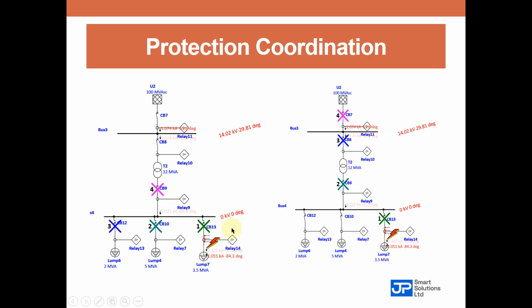But in a situation, what if this relay is no longer functioning properly? What if something happens and this relay does not react to this fault? The backup now, if it is this guy, then the fault is not cleared, the fault is not isolated, because the fault is moving like this. So it's coming to the bus bar, and that is why the ideal case is to knock off this guy.